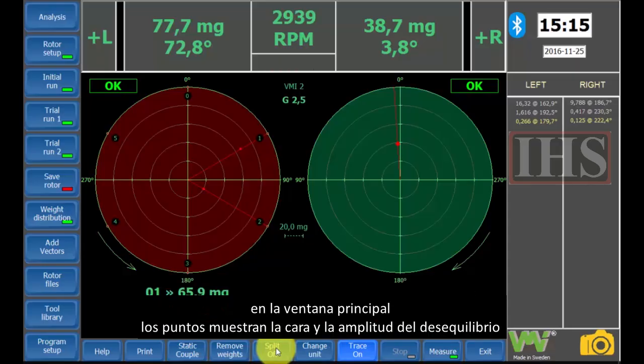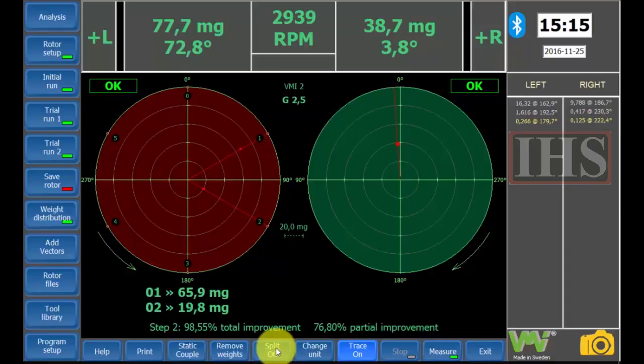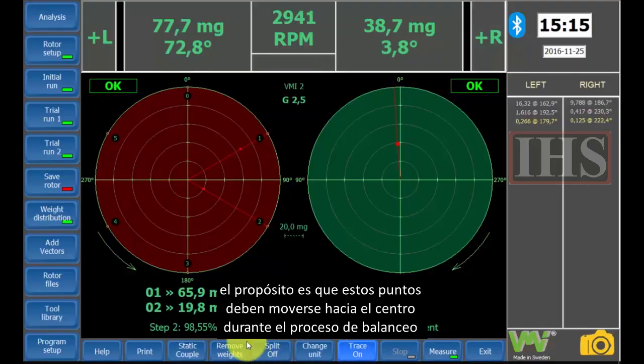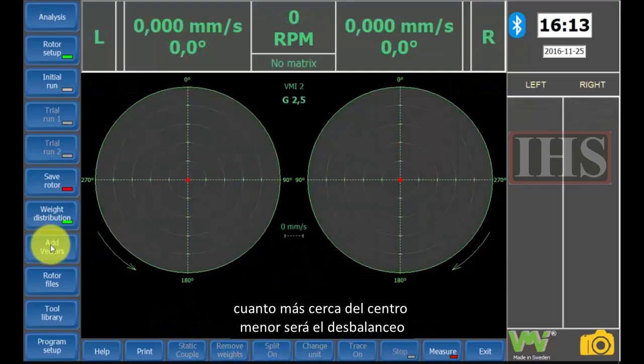The points show the phase and amplitude of the unbalance. The purpose is that these points should be moved toward the center during the balancing process. The nearer the center, the smaller residual unbalance.